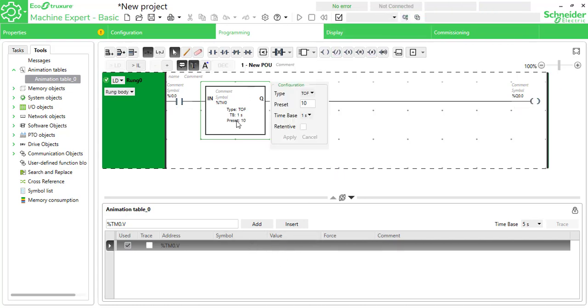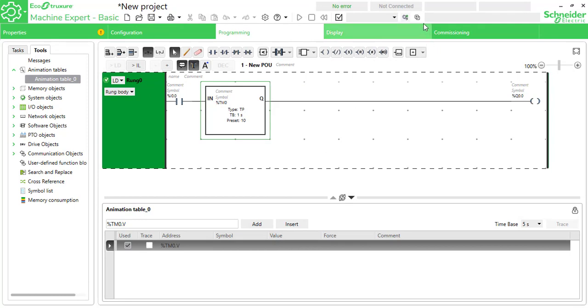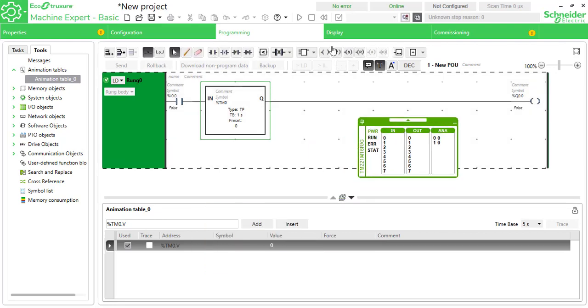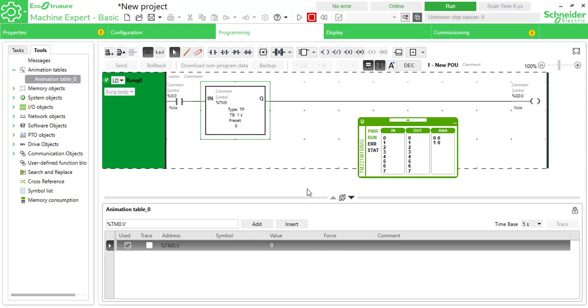Let's see the difference between off timer and pulse timer. Changing to pulse timer TP, apply and run. Give a pulse — on and off. When it is on and off, you'll get supply for 10 seconds. The output remains on for 10 seconds — that is a pulse timer, which needs just one pulse for the entire operation.